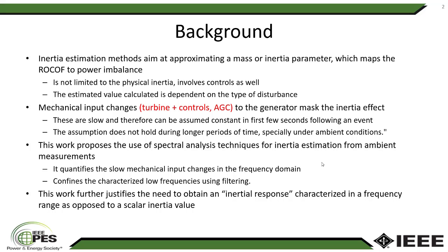But doing so in ambient conditions is extremely hard, just because in ambient conditions you don't have the luxury, you can't decompose your time window into portions with and without inertia. So therefore, in this work, we propose to use spectral analysis techniques for inertia estimation from ambient data.